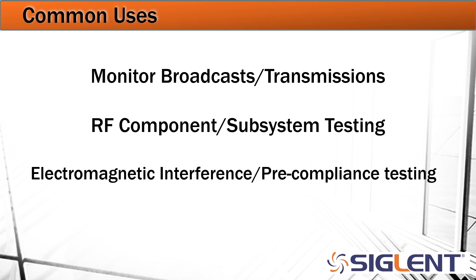Then we've got electromagnetic interference and pre-compliance testing. This is a little bit more specialized — for companies or people that happen to be ready to sell their product. Governments regulate the amount of RF output over particular frequency ranges that a product is allowed to emit. We want to make sure we're underneath that limit line before selling, because non-compliance can lead to recalls, fines, and other problems.